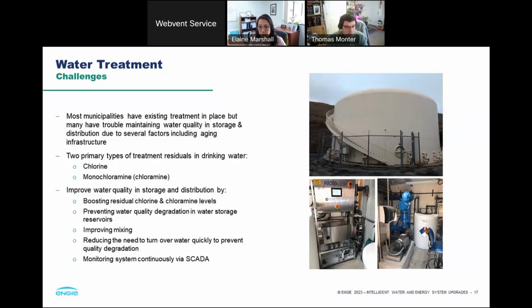In addition, we were able to integrate all those tank systems into the new SCADA system, so they can monitor water quality and tank levels and understand all the facets of the tank operation at those reservoir sites. It's been a great improvement for the city's ability to monitor systems, and if they get an alarm now, they don't necessarily have to immediately go up to the site. They can just decide whether a call is necessary at that time.